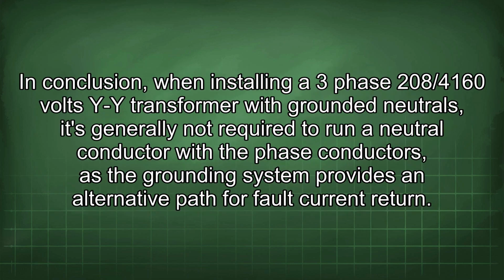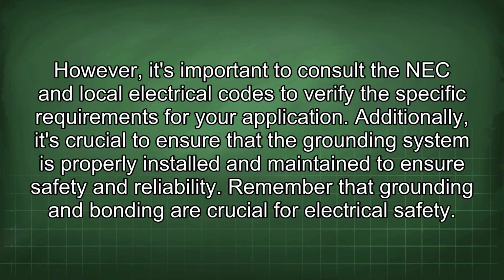In conclusion, when installing a 3-phase 208/4160 volts YY transformer with grounded neutrals, it's generally not required to run a neutral conductor with the phase conductors, as the grounding system provides an alternative path for fault current return. However, it's important to consult the NEC and local electrical codes to verify the specific requirements for your application. Additionally, it's crucial to ensure that the grounding system is properly installed and maintained to ensure safety and reliability. Remember that grounding and bonding are crucial for electrical safety.